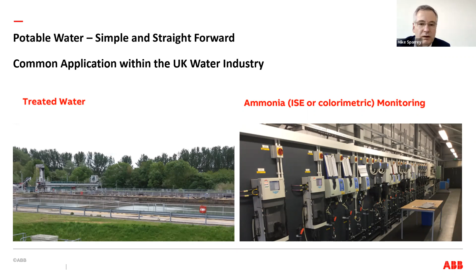The instrument itself can tolerate solids up to 100 micron, and with a flow rate between 200 and 500 mils a minute, you find that you don't really need filtration. Typically, the monitor will just run, and you would probably clean that side pot once a month, once every 2 months. Pretty easy, standard, no need for filtration.